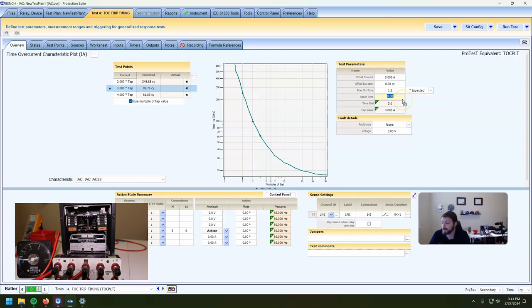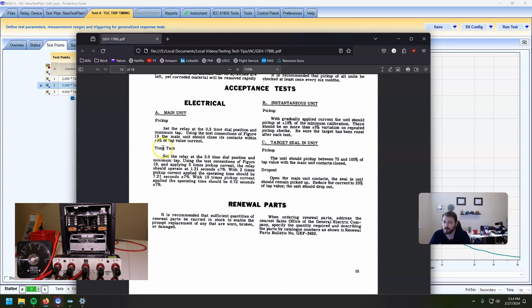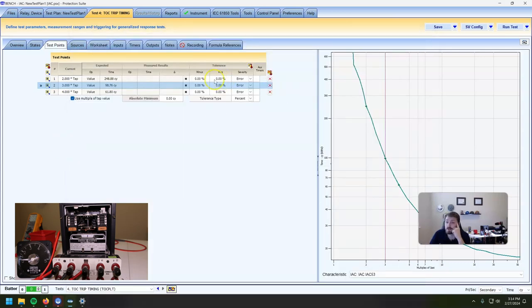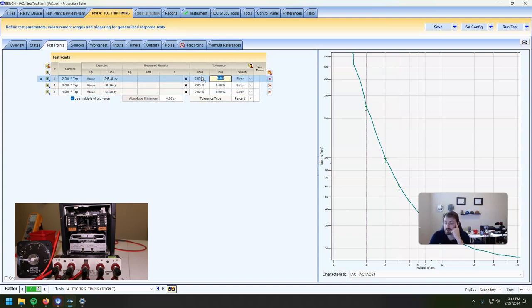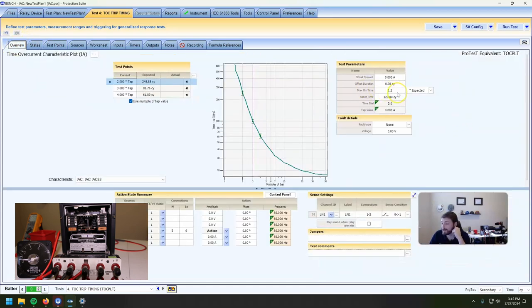The reset time — I kind of cheat it. I'll reach my finger in there and reset between the tests — give me about two seconds to reset between tests. Our test times from the relay manual say it should operate at a known good point within plus or minus seven percent. That is the tolerance we're going to use out of the book — plus or minus seven percent. Our max on time needs to be longer than that tolerance of plus minus seven percent.